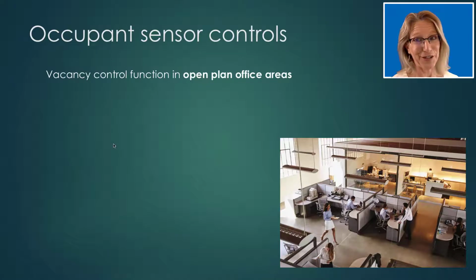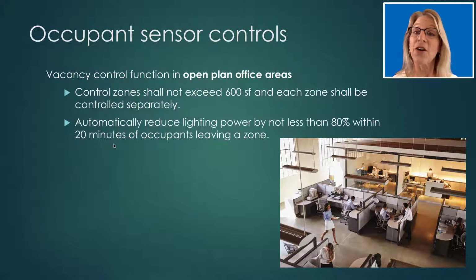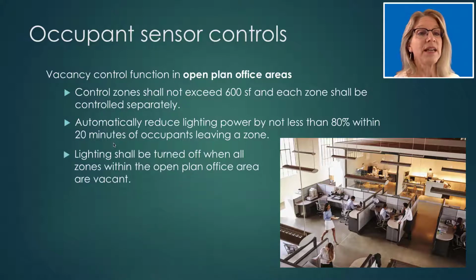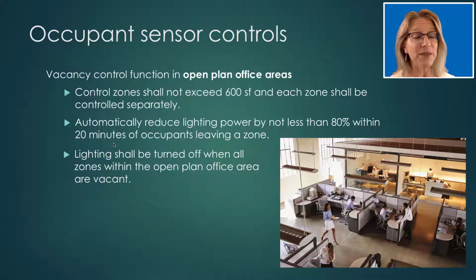Now, this is an interesting addition to the provision. Vacancy controls are now required in open plan office areas. Here's what the code states this should look like. They are required to control zones that do not exceed 600 square feet, and each zone shall be controlled separately. They shall automatically reduce the lighting power by not less than 80% within 20 minutes of the occupants leaving the zone. The lighting shall also be turned off when all of the zones within the open office plan area are vacant. So if you have a single person in their space, if they leave, the control shall reduce it down to 80%. And then when the entire area has been vacated, then all of the lights are required to turn off.